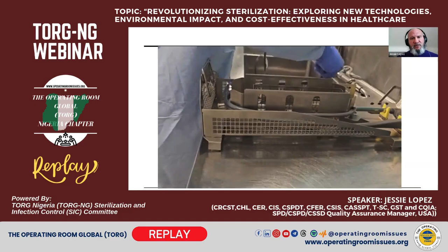We're going to neatly coil the cords in there so that all surfaces can be exposed to sterilization. We just can't throw the cord in there any which way. And again, as you can see, this takes time as well. To neatly do this, you don't want to have the cord all coiled up, overlapping itself. And then we're going to have a special placement for the actual connector. There's a little basket inside the middle of this holding tray here. And this is a tray that's provided by the manufacturer.